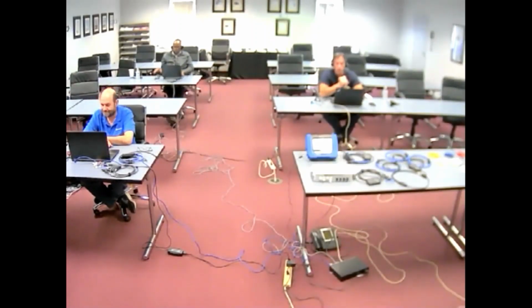It's something very unique to Dranetz, and that's the cycle by cycle comparison for changes in cycles. That was key to the generator step load testing that we discussed last week. There are 2 different ways to do it. The most common way divides a waveform up into little windows as a percentage of the 60 hertz cycle, and you compare that same window to the same window in the previous cycle.